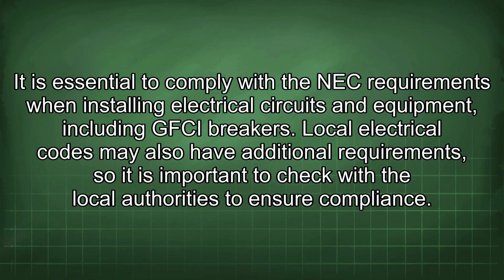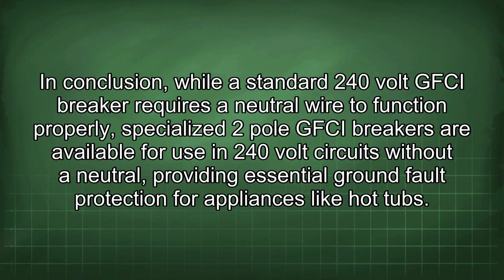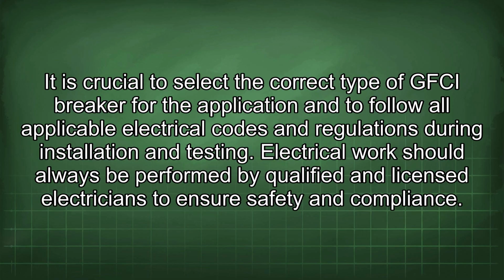ensure compliance. In conclusion, while a standard 240-volt GFCI breaker requires a neutral wire to function properly, specialized 2-pole GFCI breakers are available for use in 240-volt circuits without a neutral, providing essential ground fault protection for appliances like hot tubs. It is crucial to select the correct type of GFCI breaker for the application and to follow all applicable electrical codes and regulations during installation and testing. Electrical work should always be performed by qualified and licensed electricians to ensure safety and compliance.